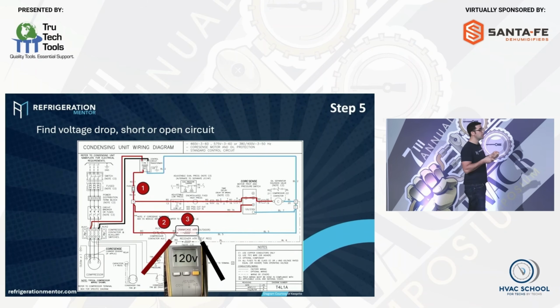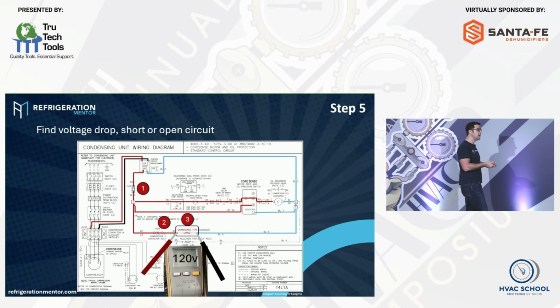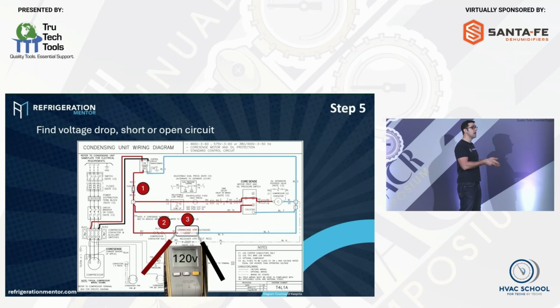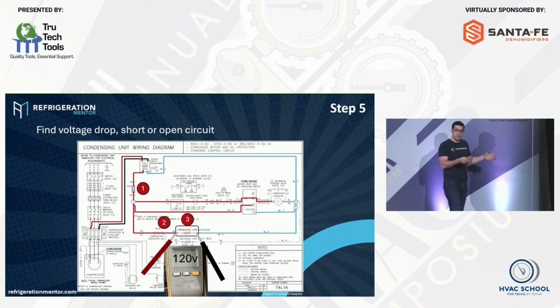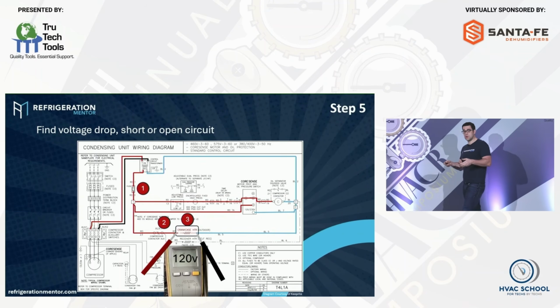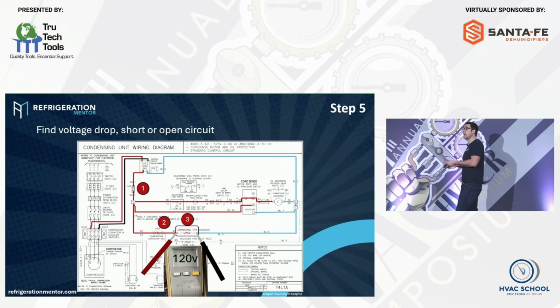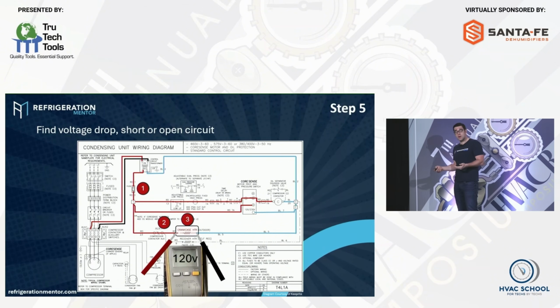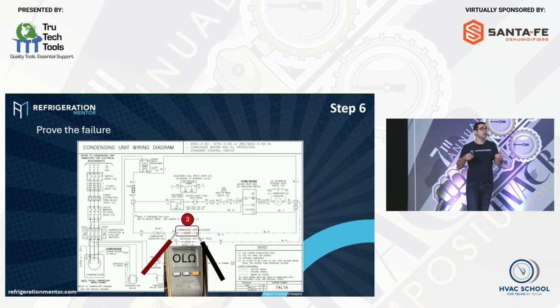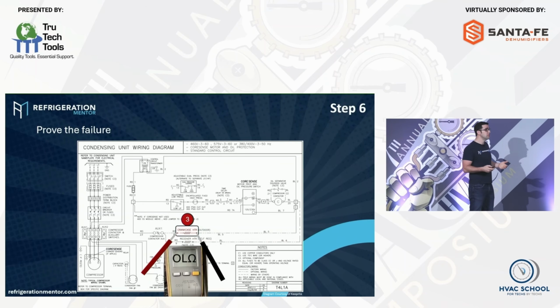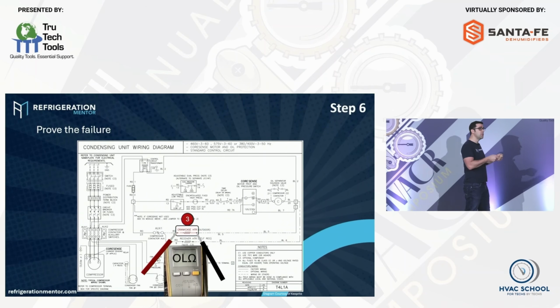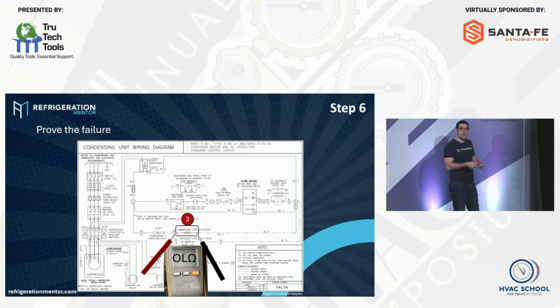Great. What's the next step? Well, then we check across that specific load that we're working on, because the crankcase heater is not coming on because we see it was flooded started when it's starting up. So we go check it. Okay, we got voltage across it. How come that crankcase heater is still not working? Then what we do is we prove the failure. How do we do it? We take the power off and then we ohm out that heater element. And if that is OL, is open, that is your problem there.